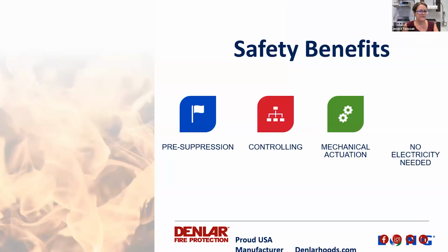So in conclusion, what all of that means is we are preventing the fire from actually occurring within the D1000 with stages of pre-suppression with temperature switches, which will activate the fan. We are controlling who has access to cooking and for how long with our clock box and the clock box pro. We are maintaining a mechanical actuation, and that's really important because there's no electricity needed in order to put out that fire, which is something that no other manufacturer in our product category can say.